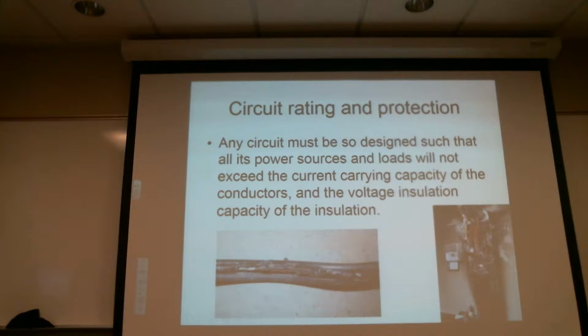Now there are some exceptions. What about high energy ignition systems? Okay, the secondary on an ignition system or a turbine igniter, now you're up in 15, 20, 30,000, 40,000 volts. Really high energy ones, 100,000 volts. You darn well better be paying attention to insulation, because at that kind of voltage, and given that the spark has a choice of going through an air gap in a very high pressure environment, which is hard for electricity to do, or leak through the insulation, it's way more inclined to leak through the insulation. Okay, so we have to pay very close attention to the insulation characteristics.